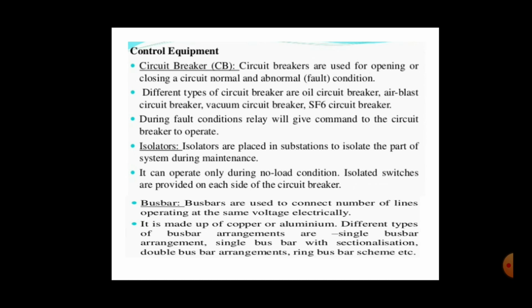Isolators. Isolators are placed in substations to isolate part of the system during maintenance. They can operate only during no load condition. Isolating switches are provided on each side of the circuit breaker. Bus bar. Bus bars are used to electrically connect a number of lines operating at the same voltage. It is made of copper or aluminum. Different types of bus bar arrangements are single bus bar arrangement, single bus bar with sectionalization, double bus bar arrangement, ring bus bar scheme, etc.